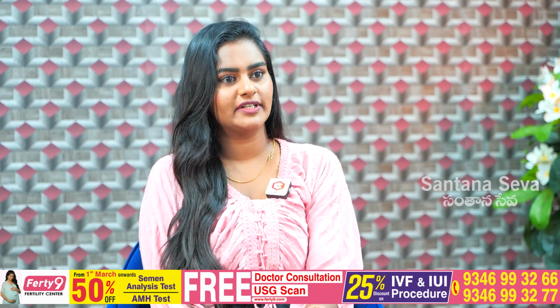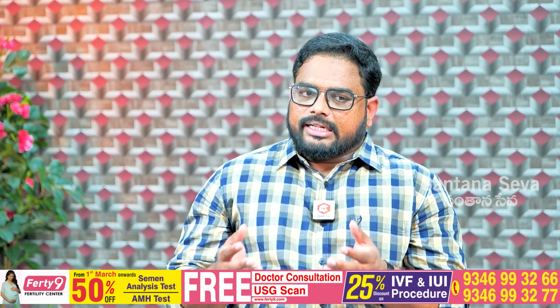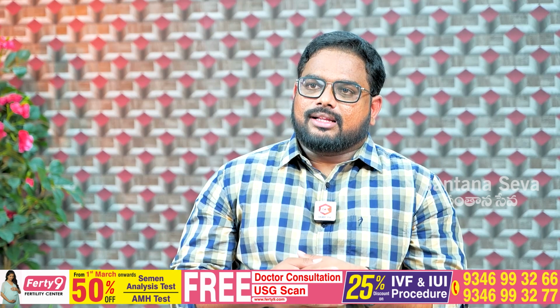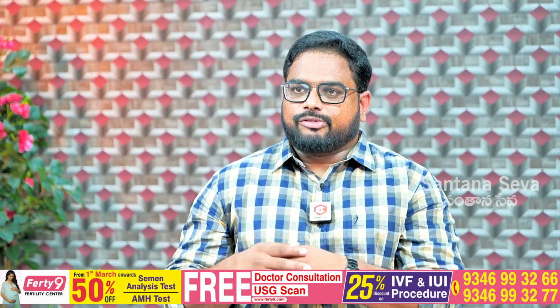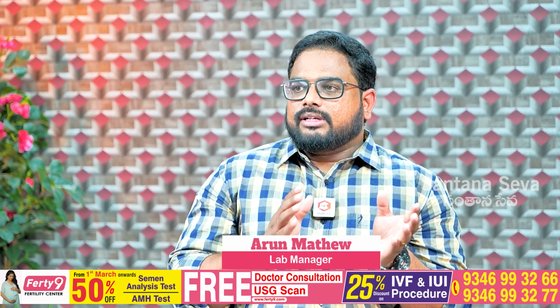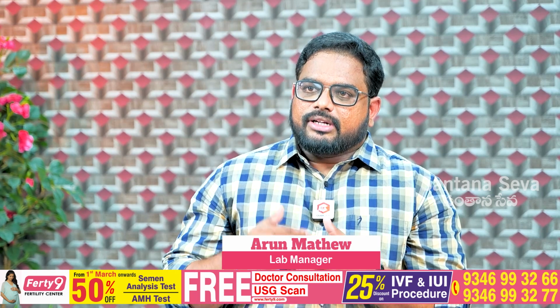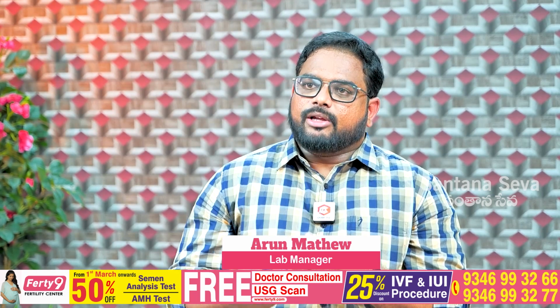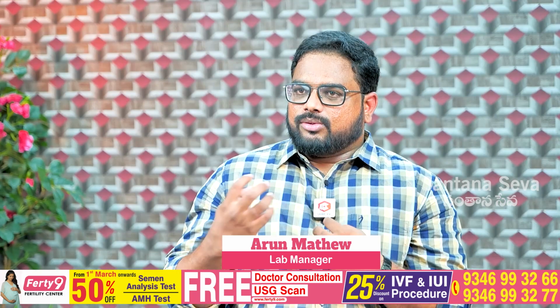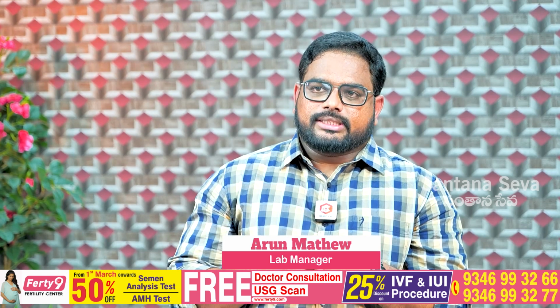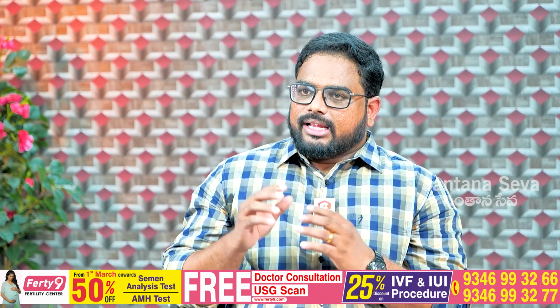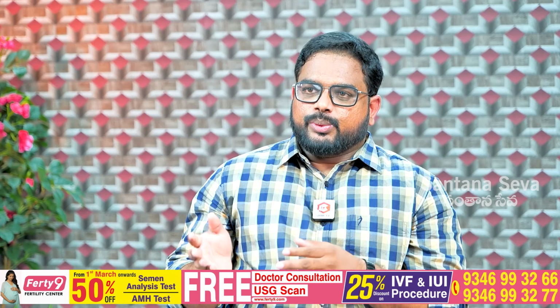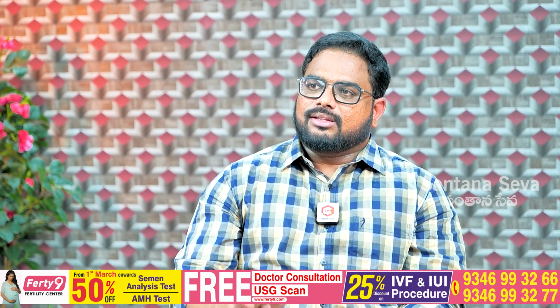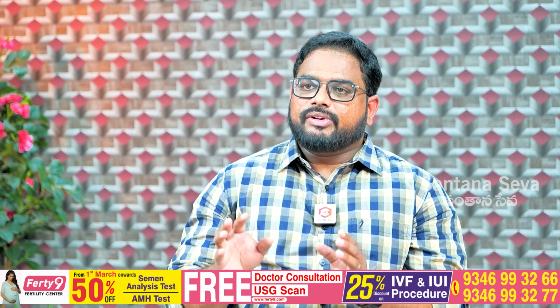So what are the advanced techniques that you are implementing in Ferty9 right now? We have many techniques and many instruments. We have a separate culture incubator for Day 5, because till Day 3 it's not a big problem. After Day 3 to Day 5 we need a separate incubator that mimics the mother's womb, so we need less oxygen supply. For that we have a separate incubator, the G210, which is one of the most advanced machines in the market as of now.